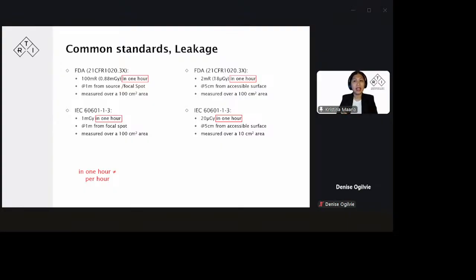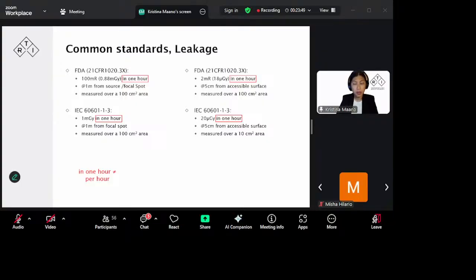So the standards say in 1 hour, not per hour, and this is to represent the maximum cumulative dose an area might receive from radiation that escapes from the tube housing, even when the tube is not actively producing an image. So this standard duration accounts for the total workload and ensures that the device is safe for staff and patient by limiting the total allowable leakage over a typical period, not just an instantaneous rate. So the values need to be normalized when we do the measurements for tube leakage. The values need to be normalized to what is plausible in 1 hour.